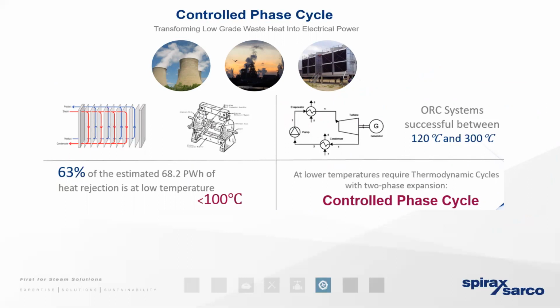And this effluent's often going to be at temperatures that are lower than most traditional methods of heat recovery can make use of. So one of the problems is that not only is this a waste of heat energy, but quite often that waste heat has then also got to go through some additional form of cooling before it can be discharged to waste. Maybe that's got to pass across a cooling tower.